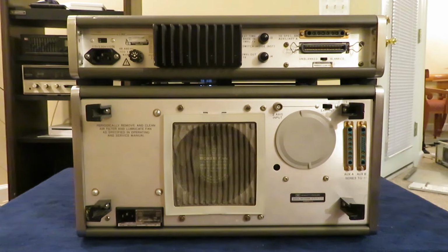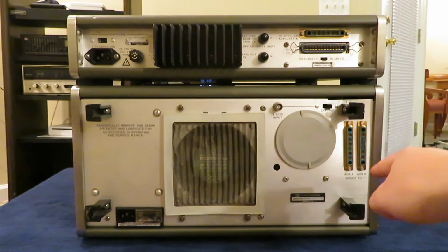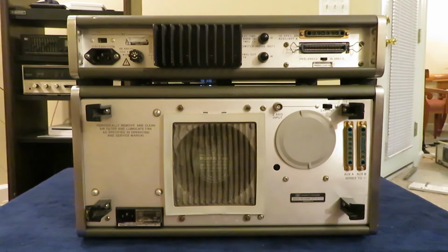Another last thing to note is not all versions of the 141 are going to be compatible with these add-on boxes. Namely the older versions, the 140A and the 140B, the 141A, the 141B, are not going to have these aux connections on the back. So they're not going to be compatible with the 8443 or the 8445, but they will be compatible with the 8444 because it only requires those front connections.